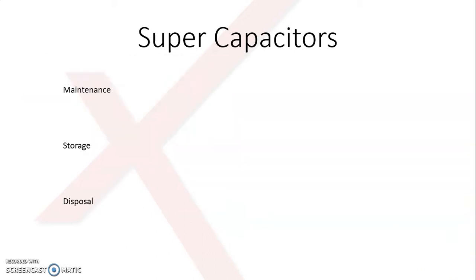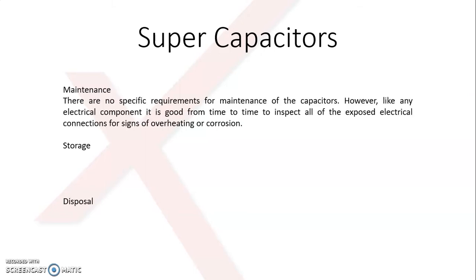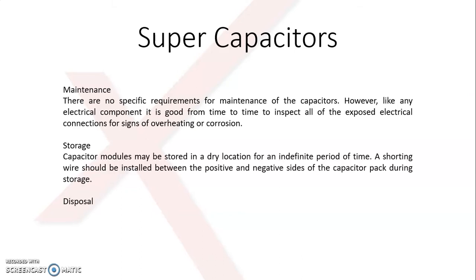So maintenance on capacitors, really there isn't any particular maintenance. However, just like any other electrical components, it's good from time to time to look at the exposed electrical connections and make sure there's no corrosion, no signs of overheating, which would indicate maybe a loose connection. So those are the types of things that should be put on a maintenance schedule or routine, just to do a visual check on the capacitors. If the capacitor module is taken out, it can be stored for basically an indefinite period of time. But that shorting wire should be installed between the positive and negative sides of the capacitor pack. So whenever it's stored, that shorting wire should be installed.